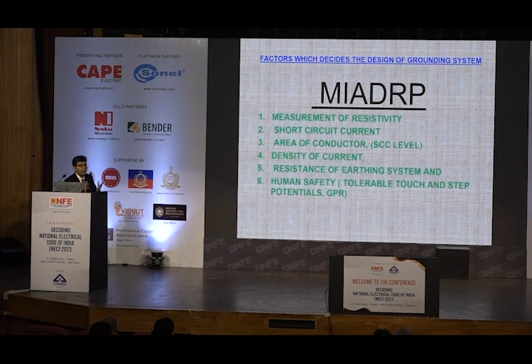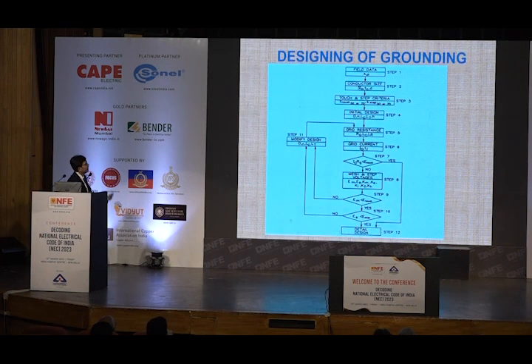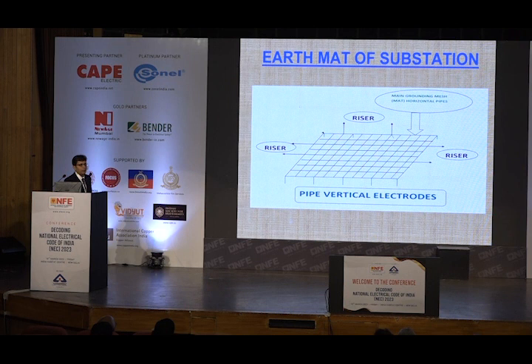And when I say designing of earthing system, it starts with a measurement of resistivity, knowledge of short circuit calculation, calculation of the area of conductor required, density of current, resistance of earthing systems, human safety that includes your tolerable touch and step potential and GPR. These are basically flowcharts to understand how the initial designs are made and checked, and finally you have to ensure the safety. When you talk about a medium voltage or high voltage substation, the earth mat, risers and equipment earthing to risers become important, and it needs proper calculation as per IEEE 80.